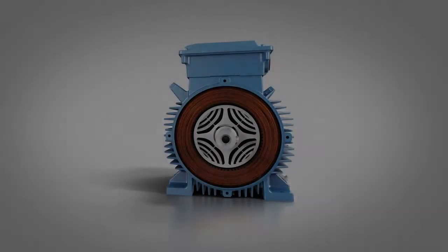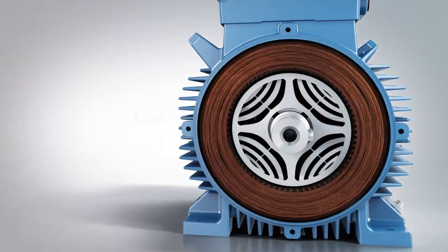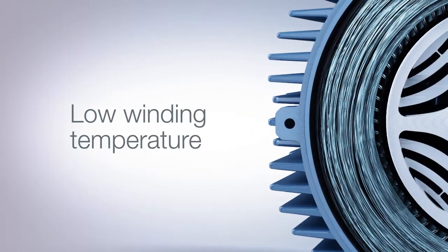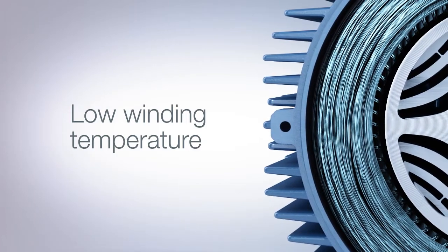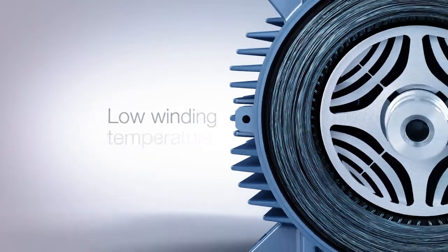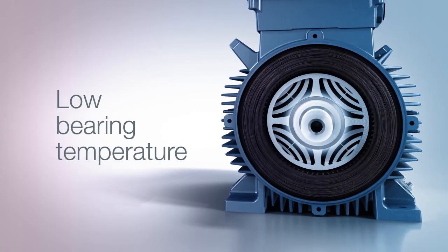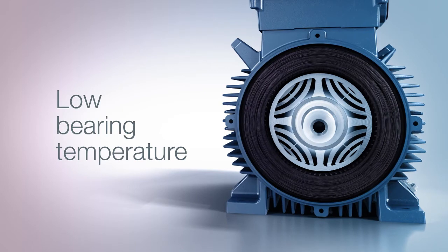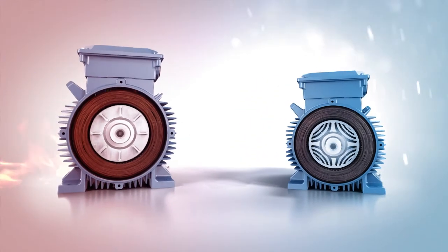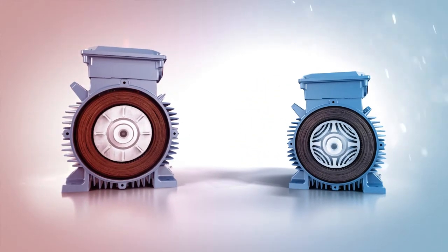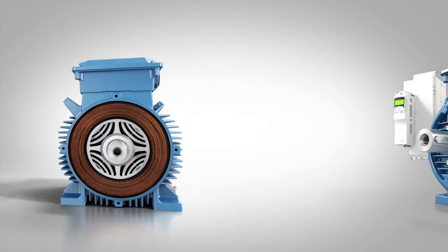IE4 synchronous reluctance motors have low winding temperature, which has a direct effect on the reliability and lifetime of the winding. More importantly, the cool synchronous reluctance rotor has a significant impact on lowering the bearing temperature. As most motor failures are related to bearings, a lower bearing temperature will dramatically increase motor reliability and reduce downtime.